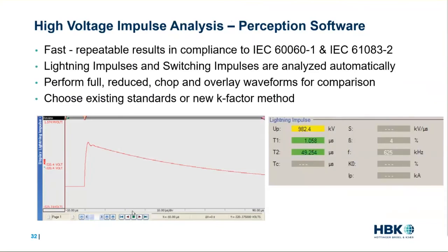waveforms can also be overlaid for comparison, for example, full and reduced, to determine any changes in their characteristics. There's also integrated pass and fail indicators with user-definable limits, and that's going to help you increase testing throughput and productivity, and you can also choose to use the existing standards or the new K-factor method.